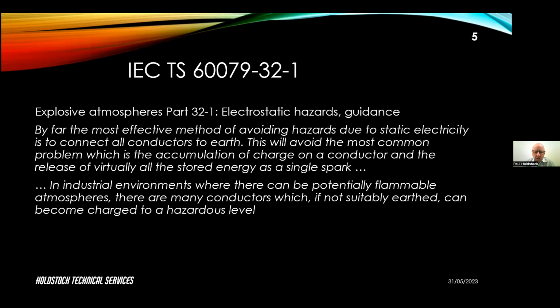In industry or in industrial environments where there can be potentially flammable atmospheres, there are many conductors which, if not suitably earthed, can become charged to a hazardous level. So this is, as it says there, the most effective, the fundamental principle: we need to make sure that all conductors are correctly earthed. Now that you'll find throughout all codes of practice and all standards related to electrostatic hazards. So it's one of the fundamental principles of controlling electrostatic hazards.